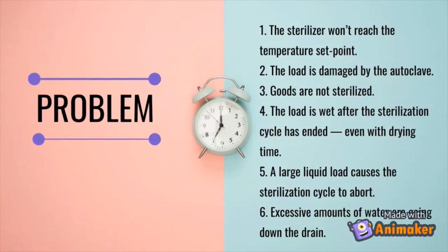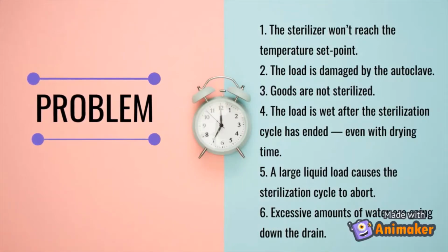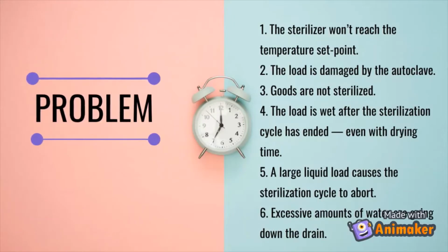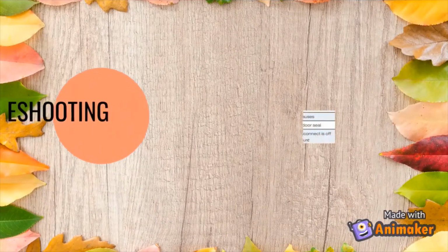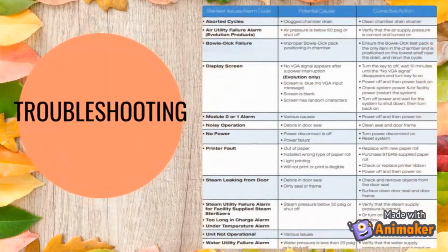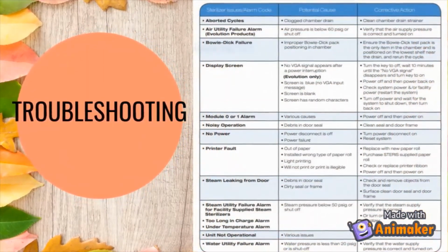Fifth, a large liquid load causes the sterilization cycle to abort. Sixth, excessive amounts of water are going down the drain. Troubleshooting: the table shows the problems faced and the corrective actions that should be taken.